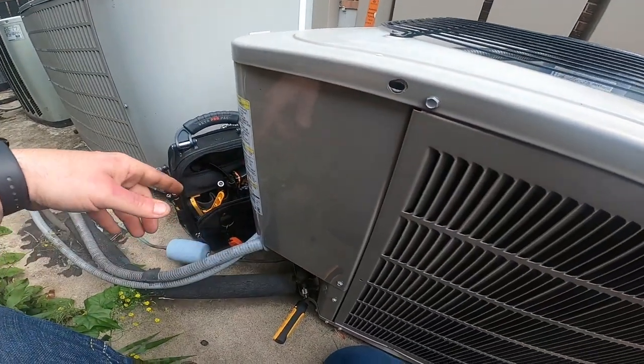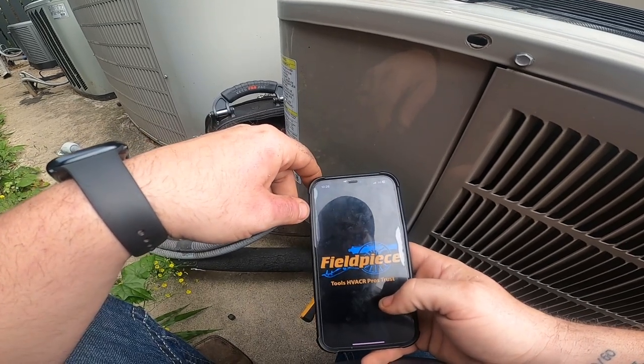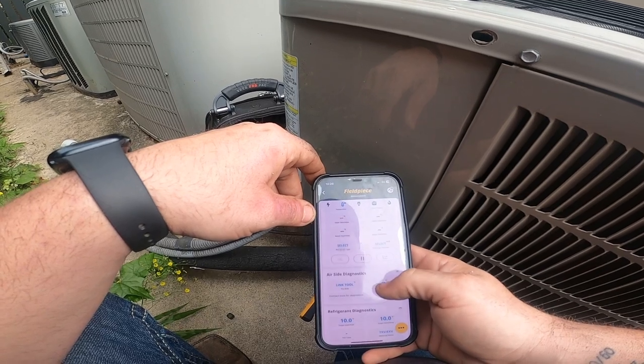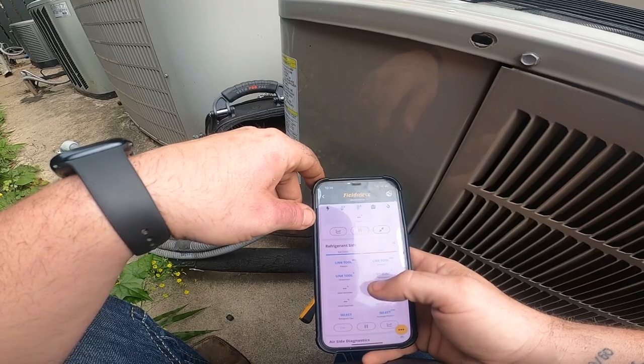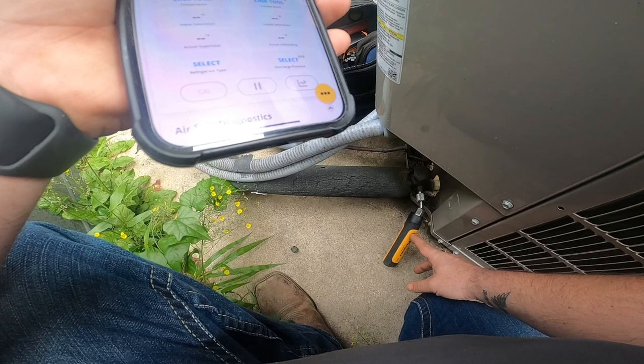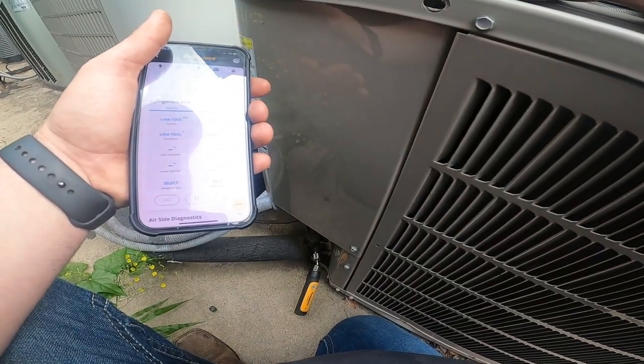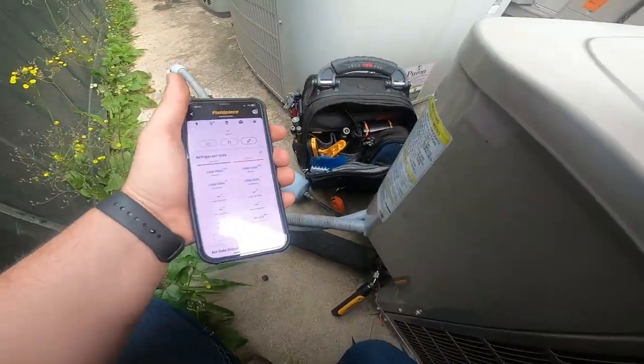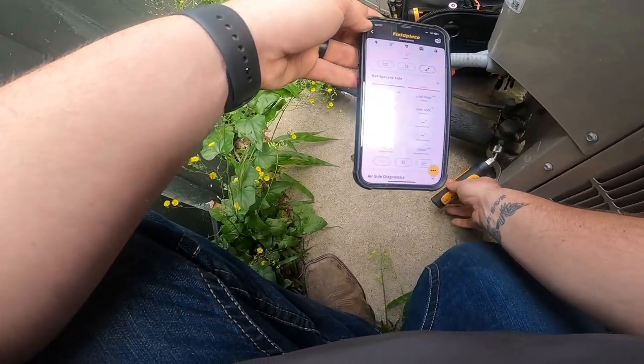Let's just see what that suction pressure is. For some reason it's - oh, don't tell me my tool went dead. There we go. We're looking for 410A readings. It looks like my tool keeps dying - I've got to send this probe back to Fieldpiece. This thing eats batteries.